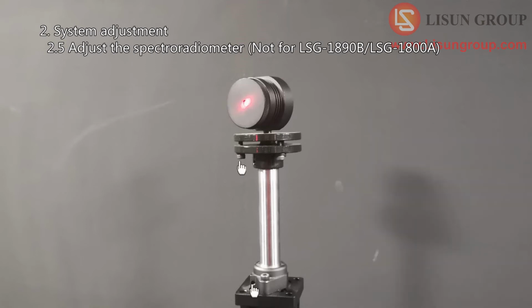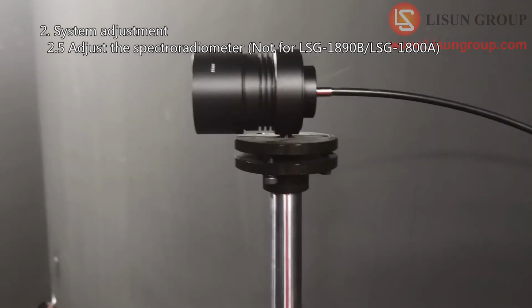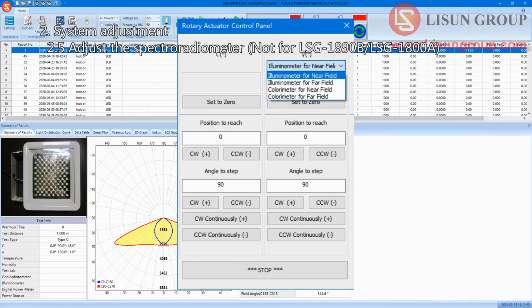All the screws should be tightened after the adjustment. After the adjustment, remove the mirror tool. Keep the optical fiber always fixed in the sleeve. Now the laser goes to the optical fiber. This position is the 0 degree position for the spectroradiometer.